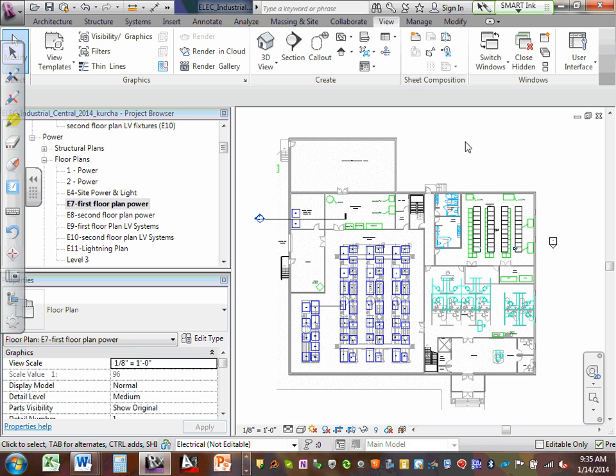Now, when you read the code, I'm going to throw you a curveball. Code says that if it's fully sprinkled, and we assume that this building is fully sprinkled, it does not require a fire alarm system for either occupancy. Now, what do we do? For the sake of the project, I think any good fire alarm practice would be to provide a fire alarm system, even though it is not required by the code. And you also want to notify the fire department that there is a fire condition in the building. No doubt about that.